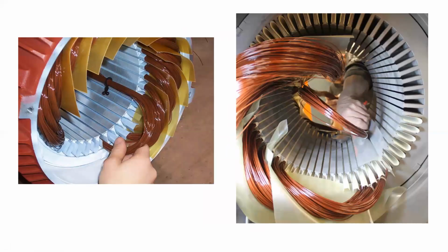Instead of having bars that fit inside these tiny little laminated plates, we have windings of motor wire. And motor wire looks much different than the standard type of wire that we use in most of our electrical installations. You'll notice here that the wire has been formed into a specific series of loops. The number of loops is important. The orientation of the loop is important in the stator. The direction of the wrap is important. And all of this is taken into consideration when the motor is designed.